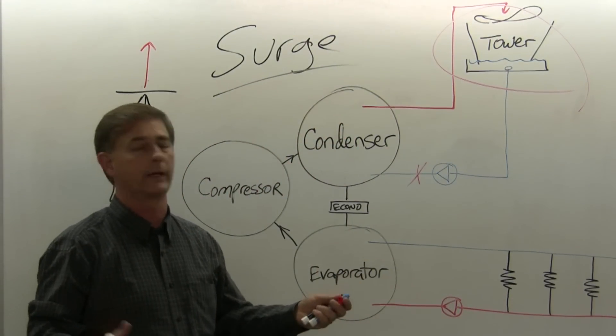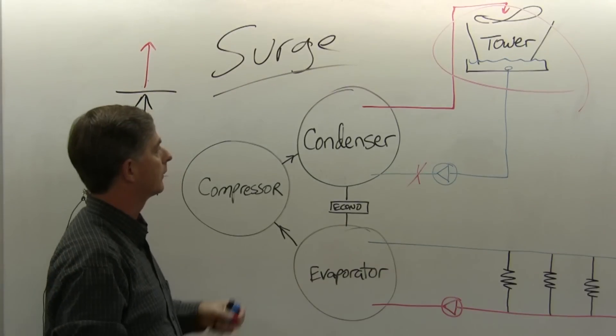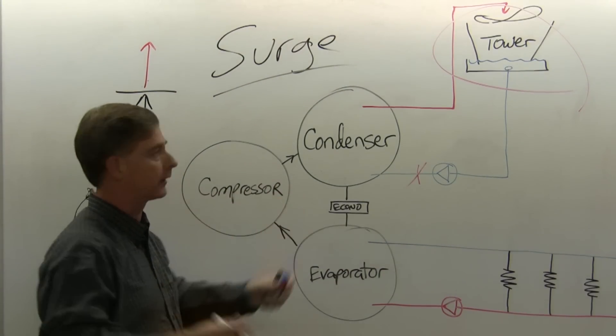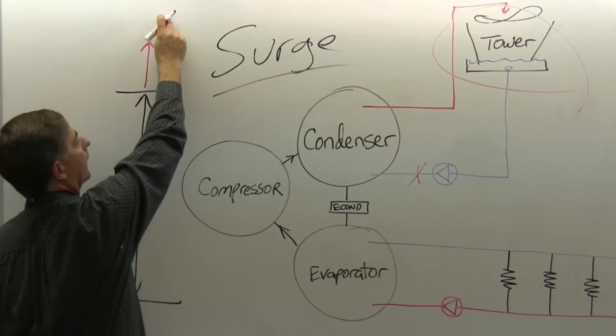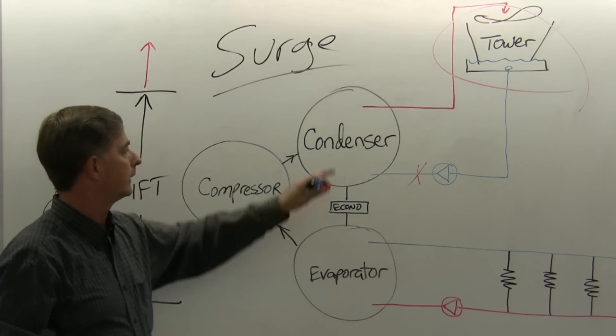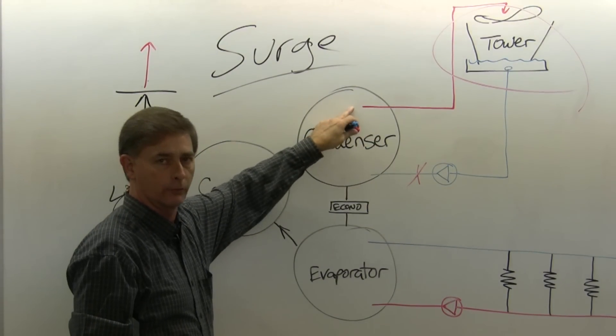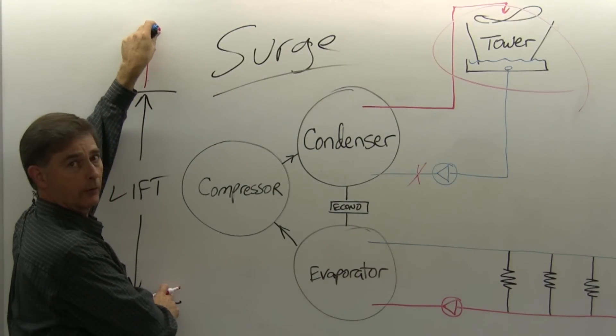Same thing, tower fan. If a fan belt breaks or transmission malfunctions or something like that, and that fan stops, you will very quickly reach a high temperature, corresponding to a high pressure, corresponding to a very large lift, you will surge.